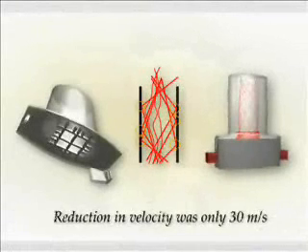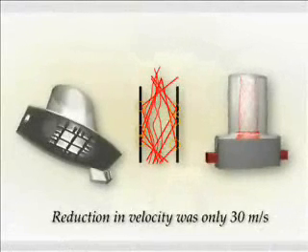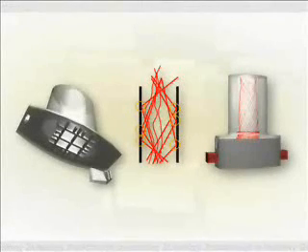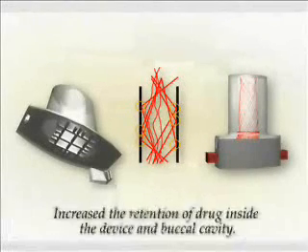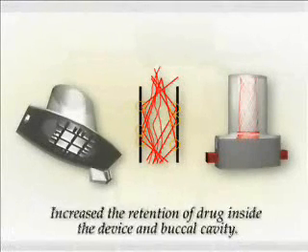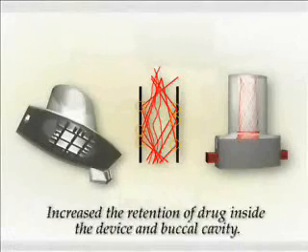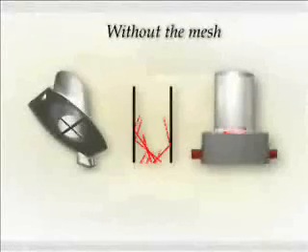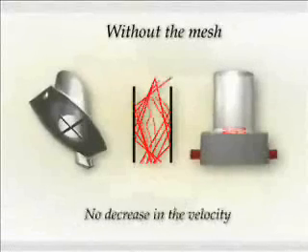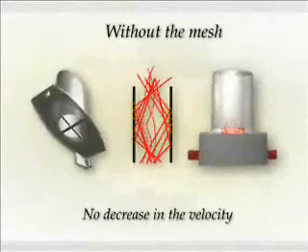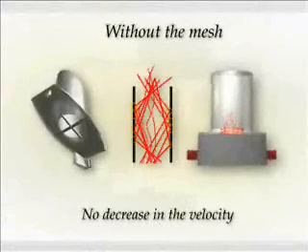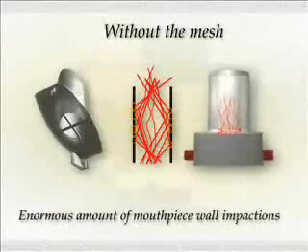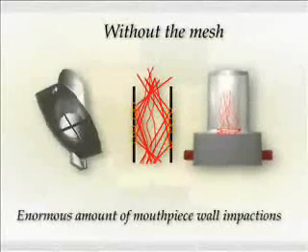Most available devices in our country have a non-uniform mesh. It was noticed that the reduction in velocity was only 30 meters per second, and therefore it increased the retention of drug inside the device and also the buccal cavity. Without the mesh, there was no decrease in velocity from the chamber to the entry or exit velocities, and an enormous amount of mouthpiece wall impactions took place, which obviously reduced the emitted dose.